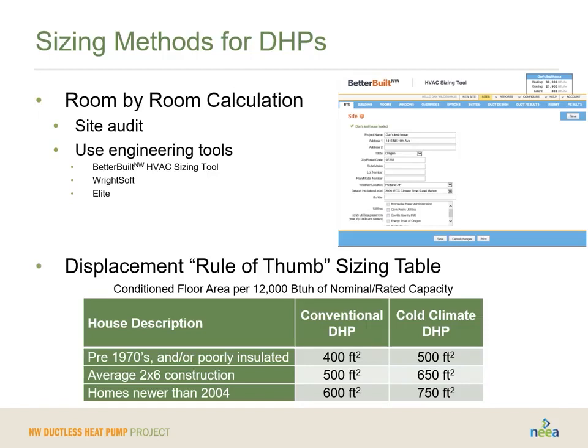In order to generate them, you do need to pay per run. So while I think that they're terrific software, I'm a big proponent of making this as easy as possible for you. So considering the BetterBuilt Northwest HVAC sizing tool might be a good place to start. If you're just talking about displacement in the main body only, you can use some of these rule of thumb sizing tables. The one we have here is just kind of indicating, a conventional ductless heat pump, what can it really treat versus a cold climate ductless heat pump. And this is for a standard 1-ton system. The older the home, the less square feet it's really going to treat really well. So if your living room, dining room, family room, main part of the hallway and kitchen is more than 400 square feet, you may want to go with a cold climate ductless heat pump unless you've got a newer or better insulated home.